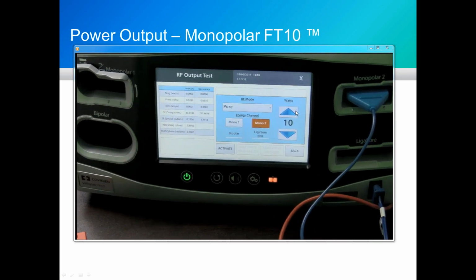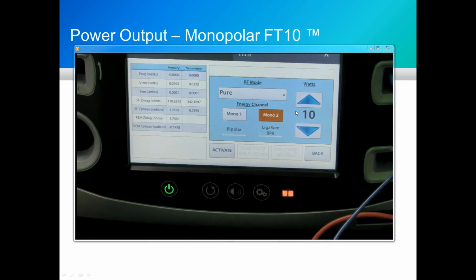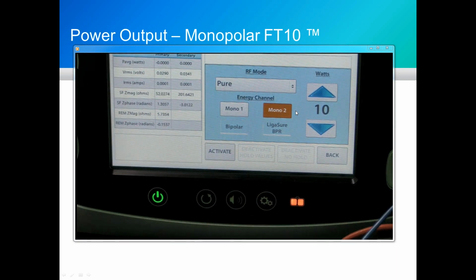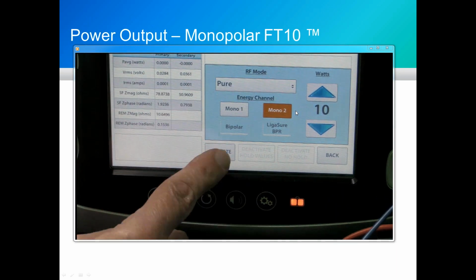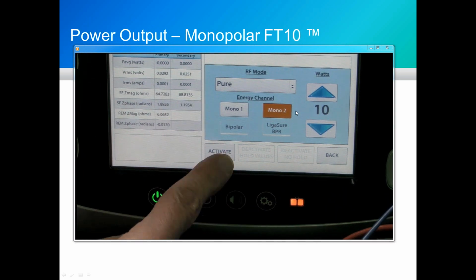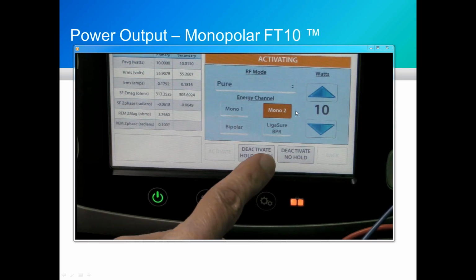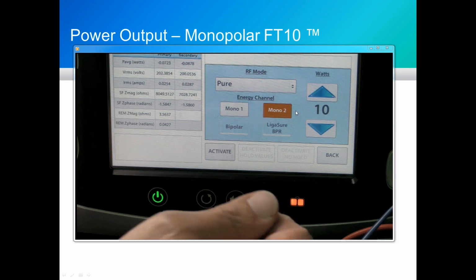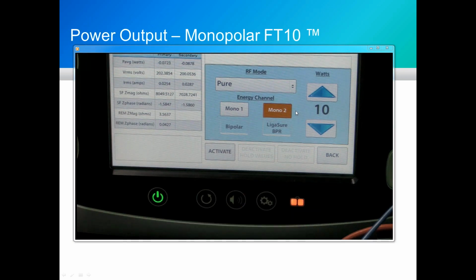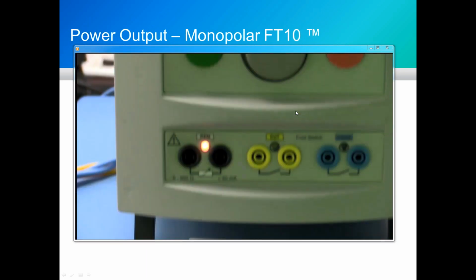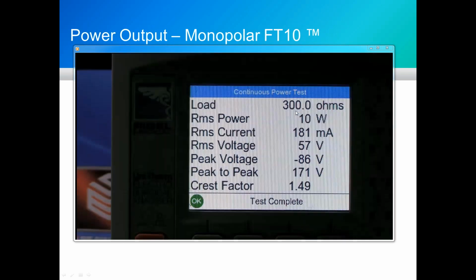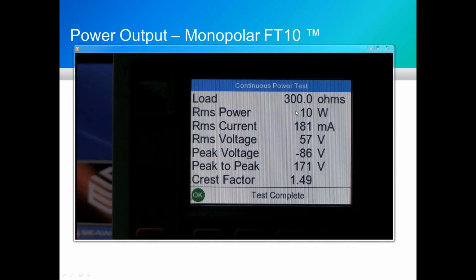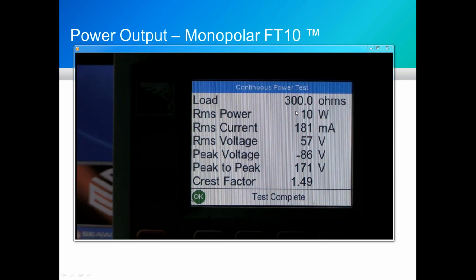Now I'm going to start my Uni-Therm measuring. I'm going to hit activate. I'm going to watch the front panel in the Uni-Therm, so while the LEDs are lit, I'm going to keep it activated. When that LED goes out, I'm going to hit deactivate. And as we go back up, we measure the same current, which is probably a good thing at this point, huh? So those are the two different ways to test.